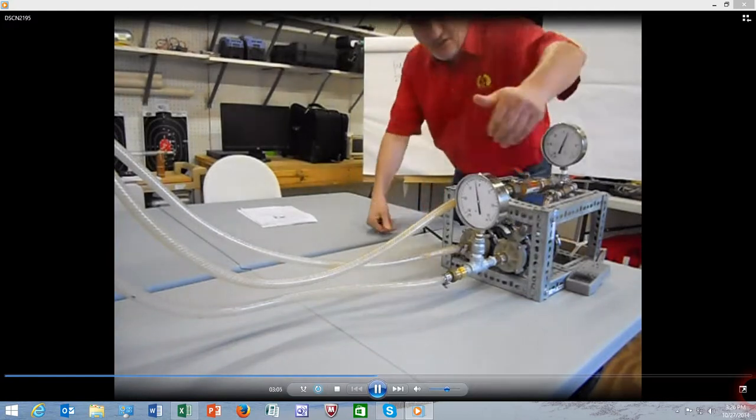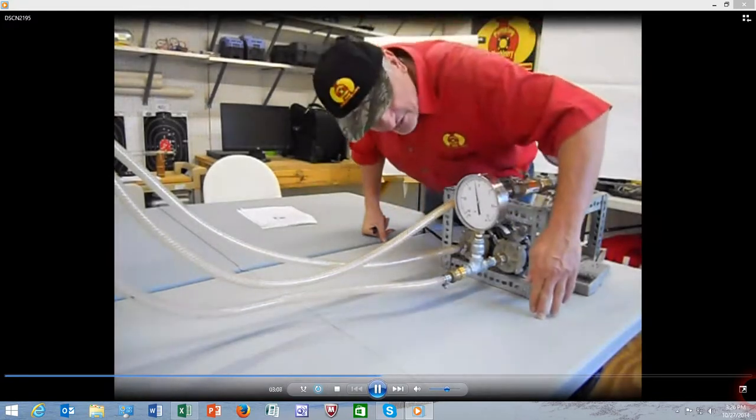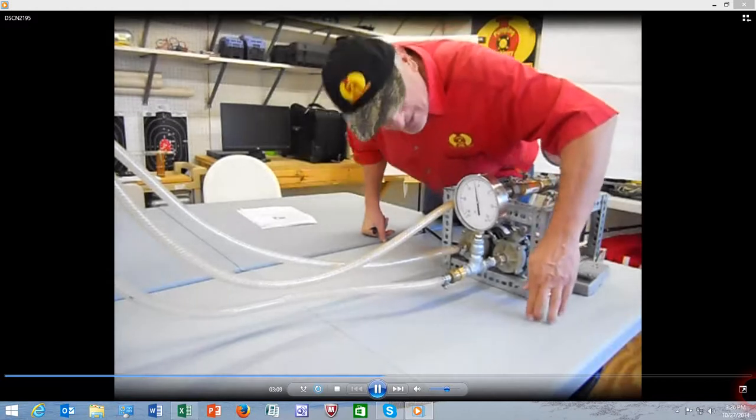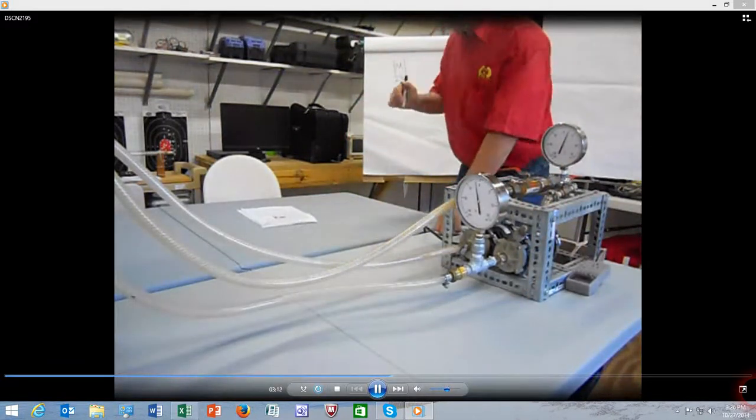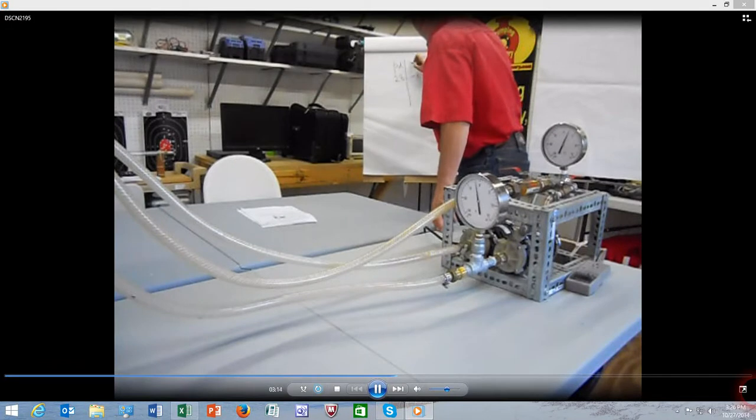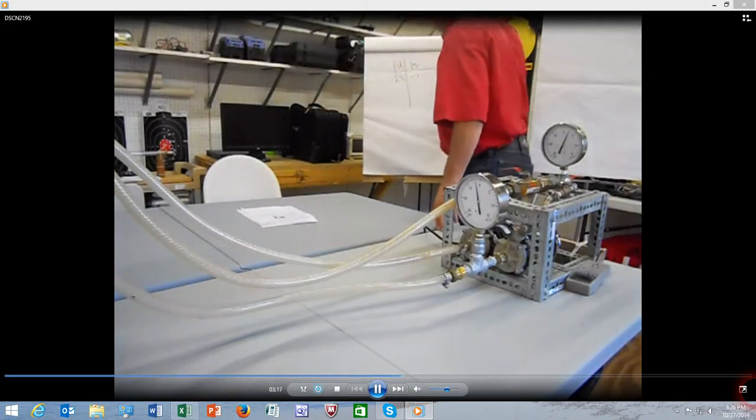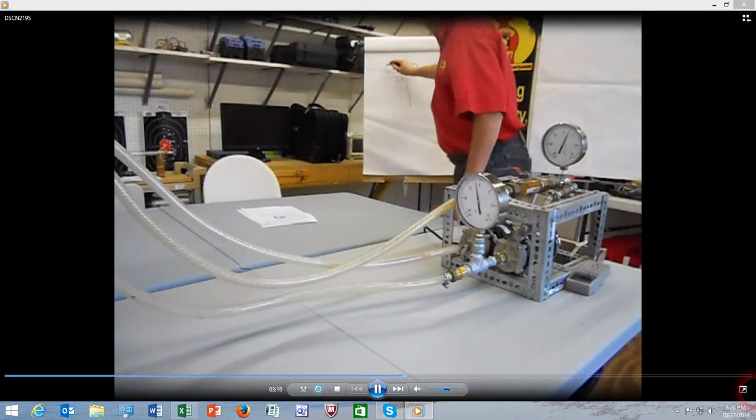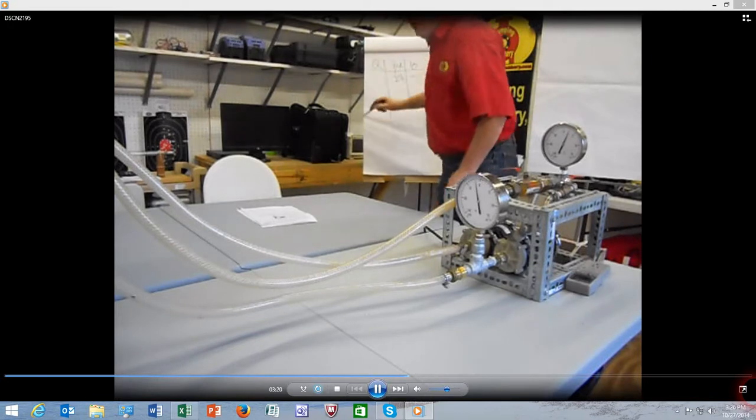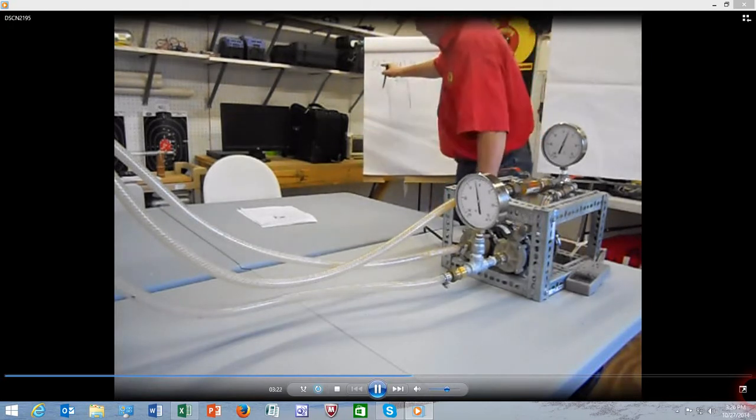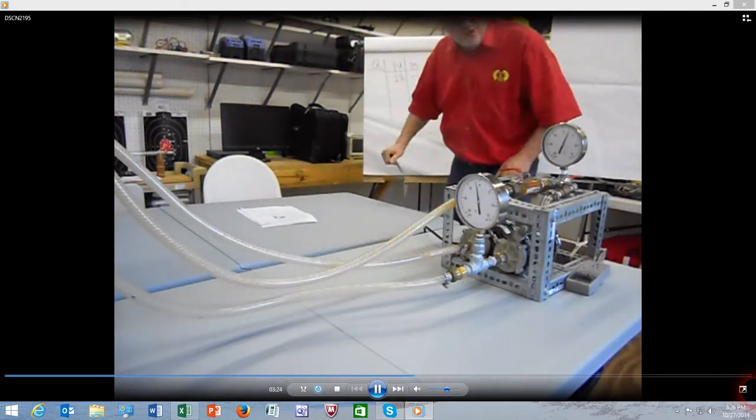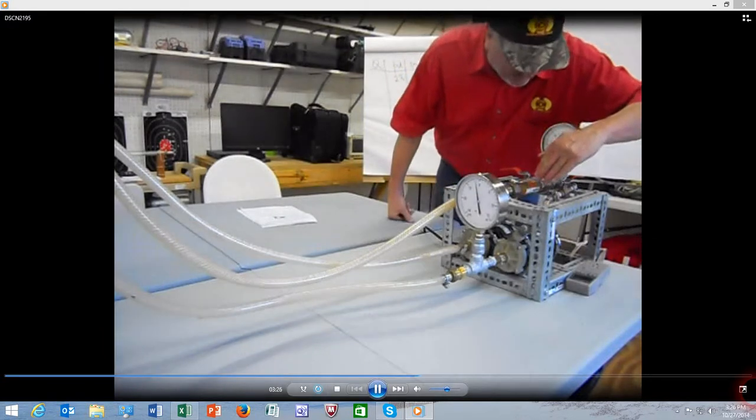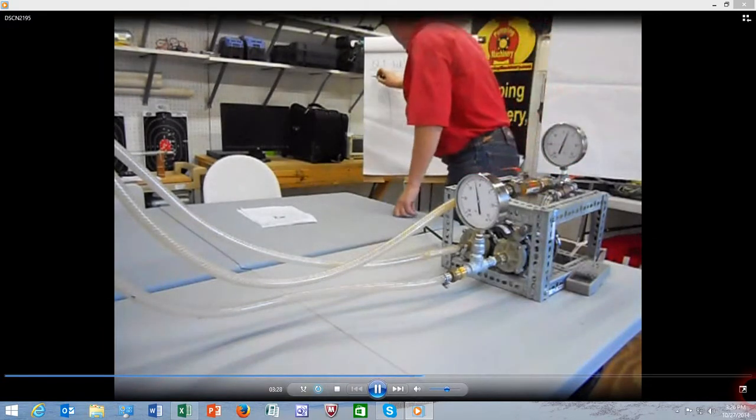The suction pressure gauge is reading negative, about 2 inches of mercury, which is about minus 1 psi. And then the flow rate - flow in pump world is denoted as Q - flow right now is about 3.2 gallons per minute.